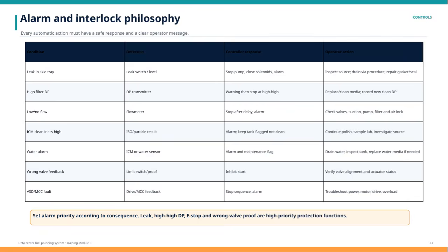It's crucial to set alarm priorities based on the consequence of each condition. High-priority protections include leaks, critical high differential pressure, emergency stops, and wrong valve feedback. These ensure that the most dangerous or impactful faults are addressed immediately to maintain system safety and reliability.